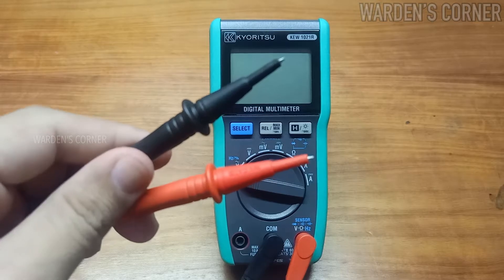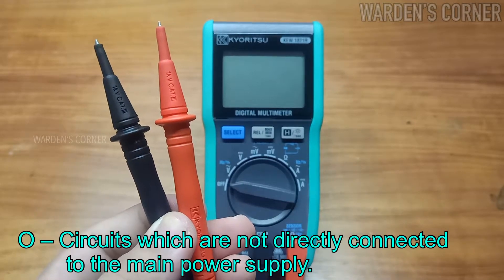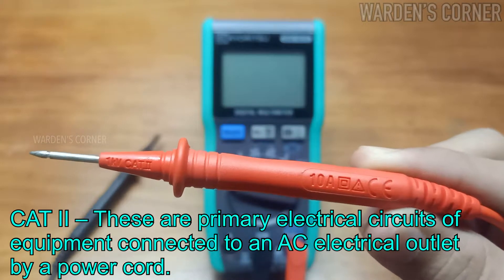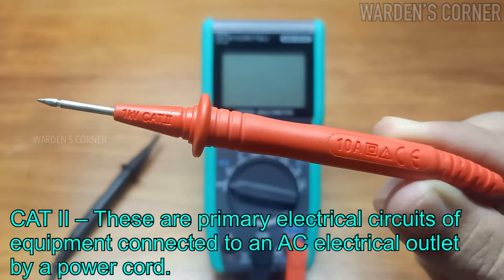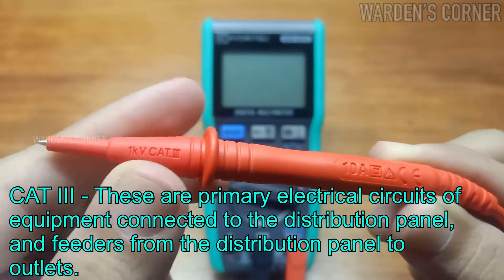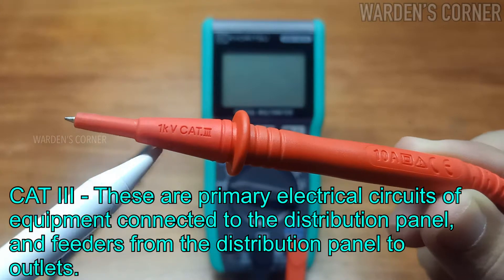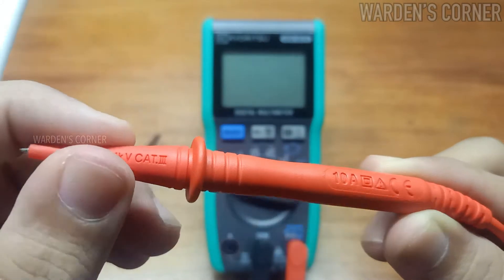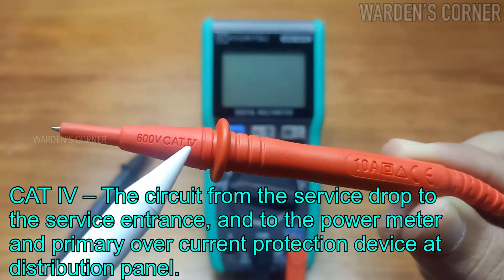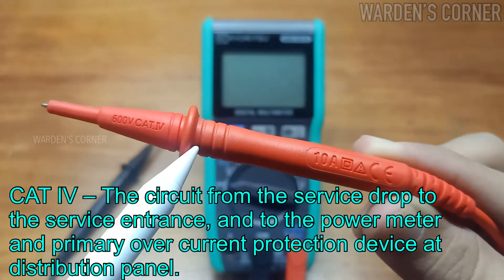These are the measurement categories. CAT I: circuits not directly connected to the main power supply. CAT II: primary electrical circuits of equipment connected to an AC electrical outlet by a power cord. CAT III: primary electrical circuits of equipment connected to the distribution panel and feeders from the distribution panel to outlets. CAT IV: the circuit from the service drop to the service entrance, power meter, and primary overcurrent protection device at the distribution panel.